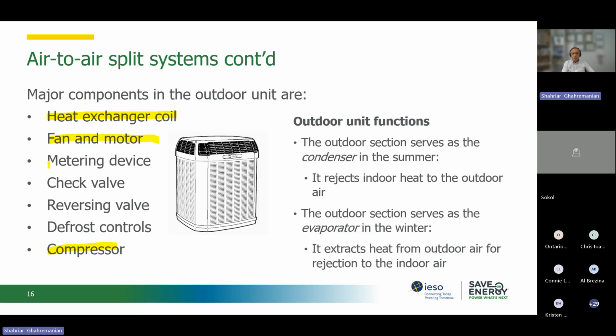So that's another way we can differentiate heat pumps from air conditioning, because an air conditioner only rejects heat, so it is going to have the fan upward. But for heat pumps, most of the time the fan is on the side. So this is one of the components I told you about, the reversing valve, which is added to our air conditioning cycle. Then it becomes a heat pump. The other thing is that during the winter season we need defrost controls as well. So we need a defrost system for our heat pumps. These are the two extra components added to our heat pumps so that they can operate during the winter season as well.